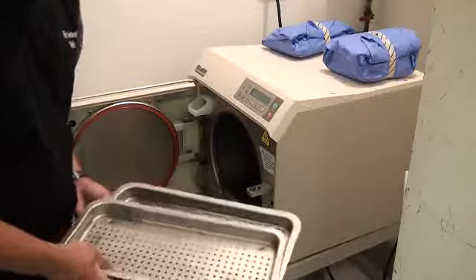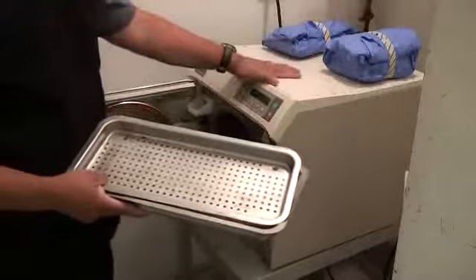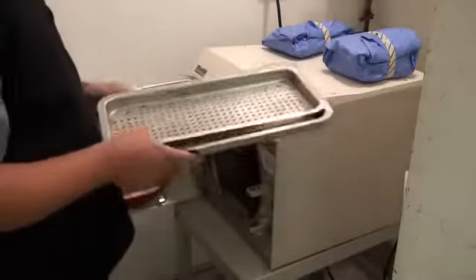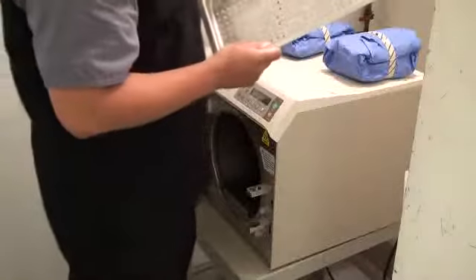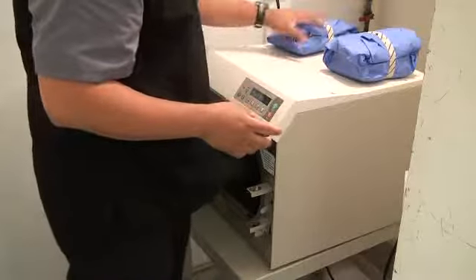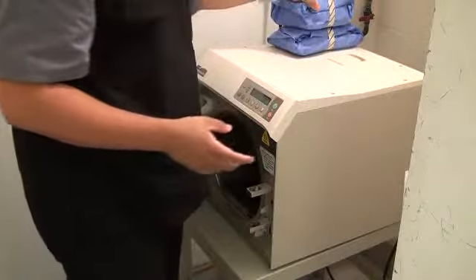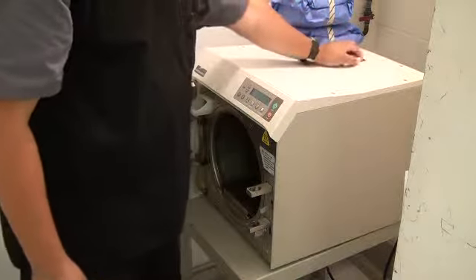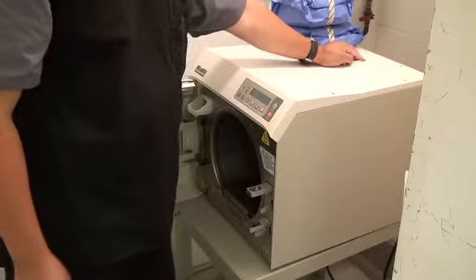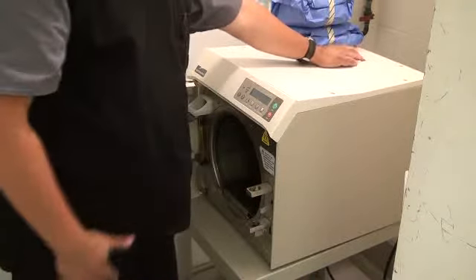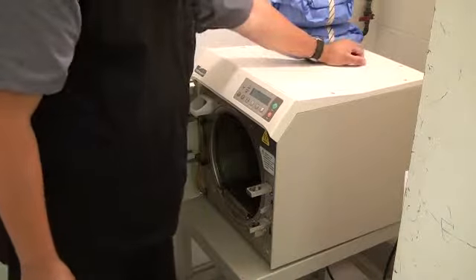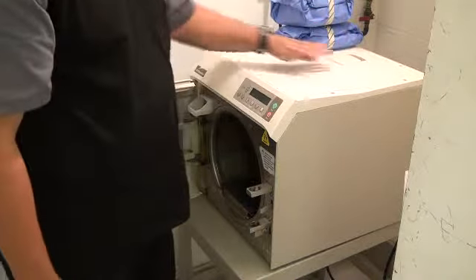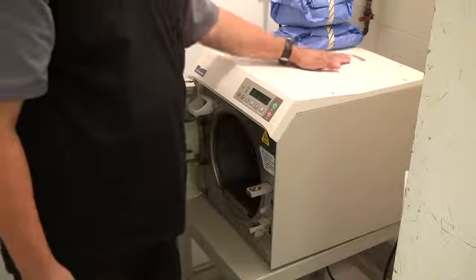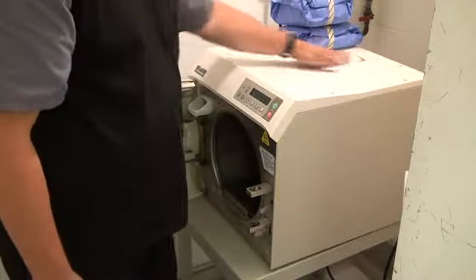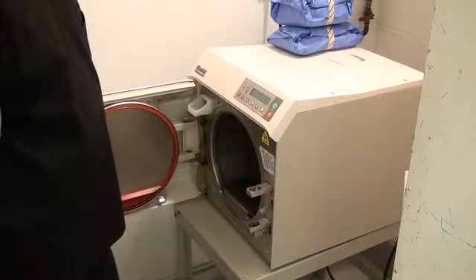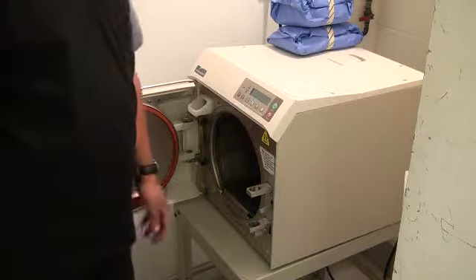These trays are removable. They should not be stored on top of the unit. They can be stored on the shelf. We'll ignore these packs for now. There is a fast emergency vent back here. In the case of the vent, you need to actually vent everything. You can just pull hard on that, and that opens up the vent. That vent should be checked occasionally before each cycle as well.